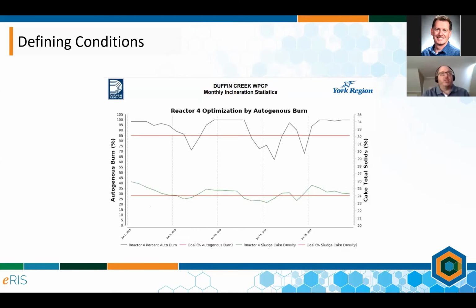So they started by using some visualization tools within eRIS, and they recognized quickly that there was an association between the autogenous burn rate—meaning when the fire in the incinerator is burning on its own, which is a fuel-saving mode—and when it drops below a certain percentage, it then requires more fuel. That situation directly aligned with times when the cake, the material being burned, was more saturated with water.